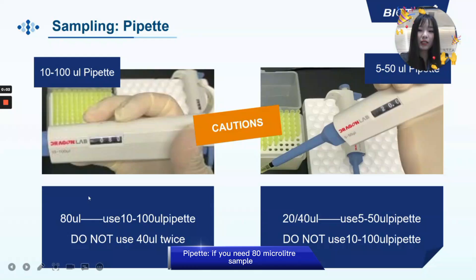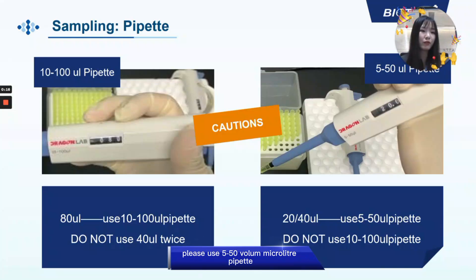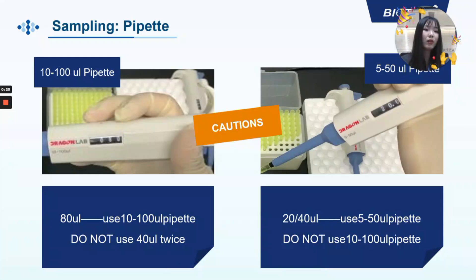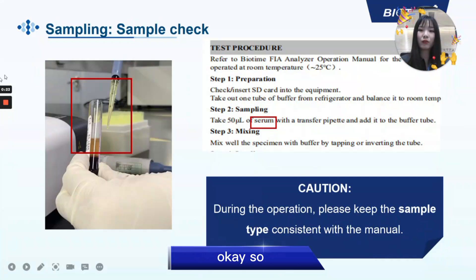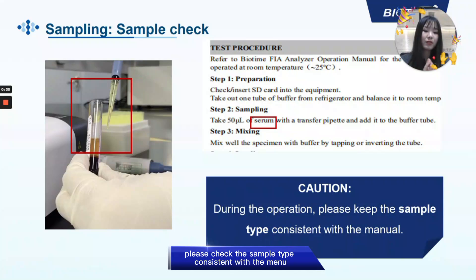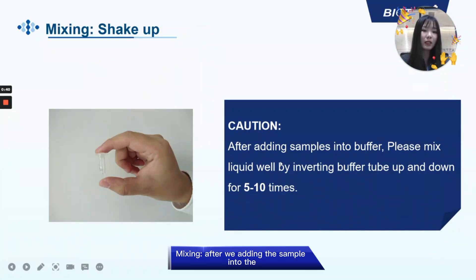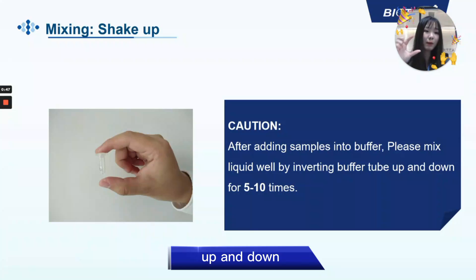Warm up: since we store the buffer at 2 to 8 degrees, please wait about 10 minutes for the buffer and sample to return to room temperature. If the sample is whole blood, please mix well before operation. Every time you bring out a new buffer, check that the liquid is clean, transparent, and has no impurities inside. If you find the liquid is contaminated, do not use it — take a new one. For pipetting: if you need 80 µL sample, use a 10 to 100 µL pipette. If you need 20 or 40 µL, please use a 5 to 50 µL pipette. Check that the sample type is consistent with the manual.